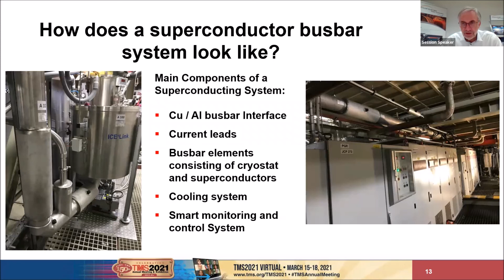On the right side, you see our busbar system installed above a switchgear. Under a ceiling above there is an electrolyzer. So the space between the busbar and the crossing pipes and the ceiling was very narrow. We had a total clearance of about 250 millimeters, and the busbar system itself is a little bit more than 200 millimeters in width. So there was just very limited space to install that. This is not possible for any other busbar system or for any other cable system. So this is one of the unique features. You see it here, very compact and conducting 20 kiloamp.